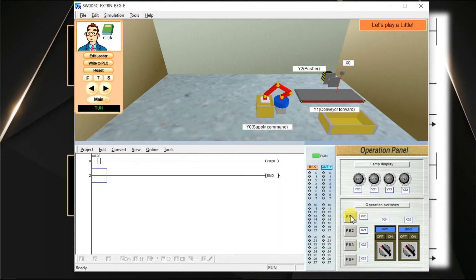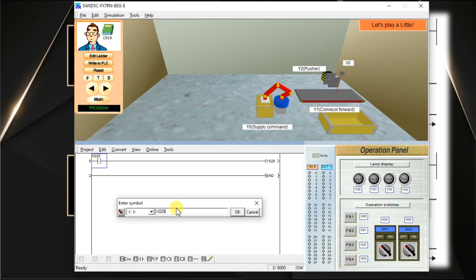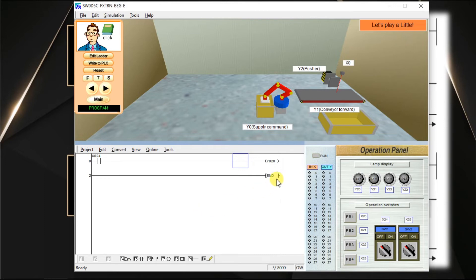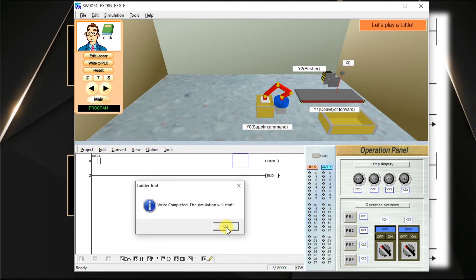Now instead of using the push button, I want to use the selector switch in this place. We have to change the input address from X20 to X24. The PLC is in run mode, so editing is not possible — we have to change to program mode. Click Edit Ladder. Double click on X20 and enter X24, click OK. Whenever there is a modification, the respective line turns grey. Compile the logic — click Convert. Everything is good. Download to PLC — click Write to PLC. Completed, press OK.